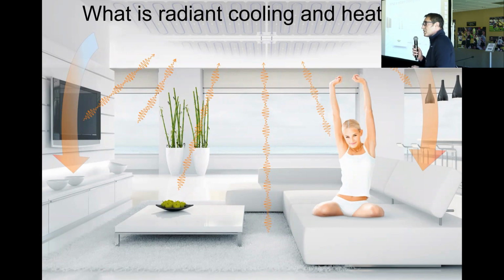You can see there are two arrows here from the ceiling pointing down. What do they represent? It's a convective cooling effect. When we are close to the ceiling, there will be a layer of air that, in touch with the cold ceiling, gets cooler, and then that cool air moves down. In a radiant ceiling system, typically there is about a 30% convective contribution, a convective phenomenon, convective cooling that helps in cooling the environment.